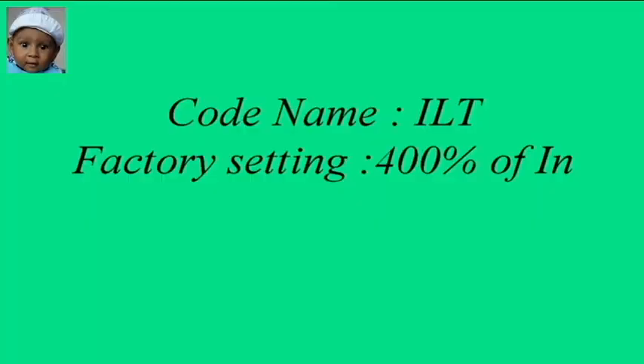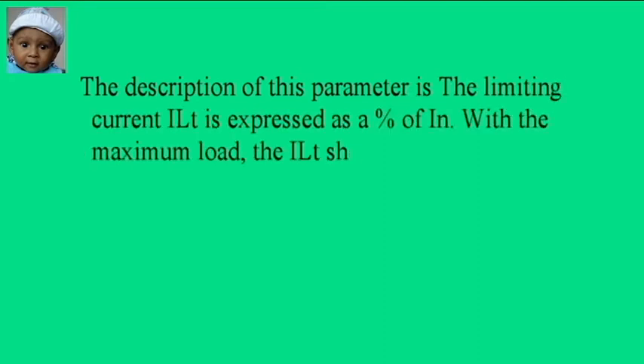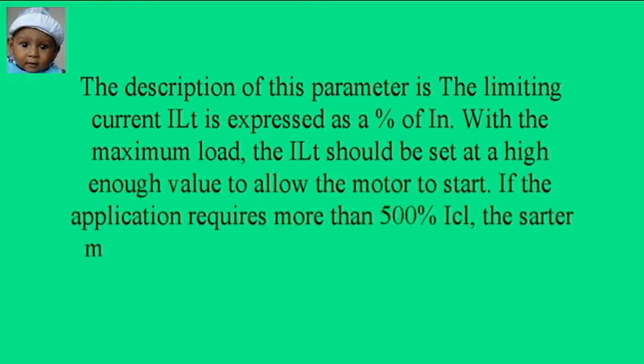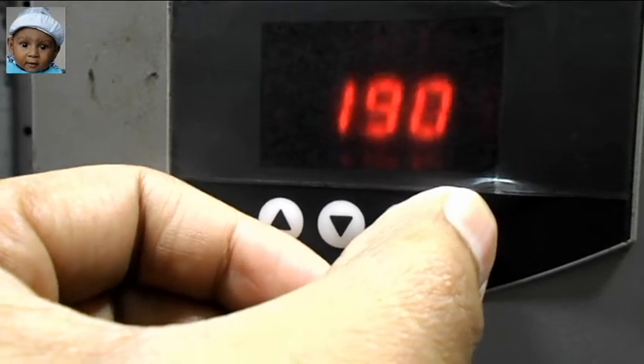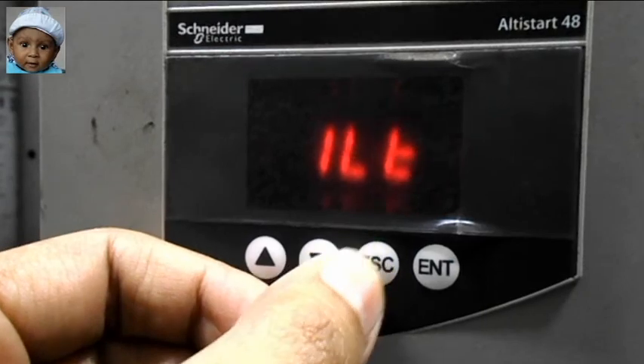Our second parameter is ILT and the factory setting value is 400% of IN. The ILT stands for limiting current and ILT is expressed as a percentage of IN. I have given two examples that show how much value you can set on the ILT parameter.